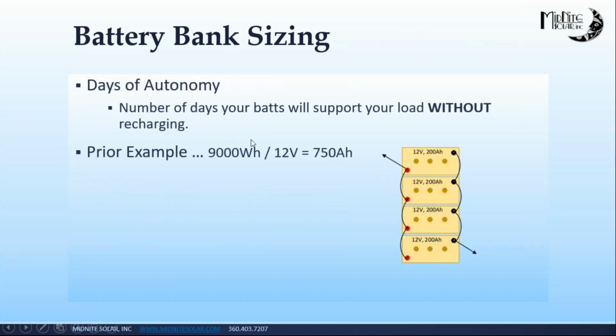Now we spoke about days of autonomy, the number of days your batteries will support your load without recharging. Going back to the load analysis, we need 4,500 watt hours for one 24-hour solar day to support your loads for you and your family. We're going to double it, using flooded or sealed batteries at 50% depth of discharge, so that's 9,000 watt hours. We've decided to stay in 12 volts, so I need a 750 amp hour battery bank. These 4 batteries will give me 1 day of stored energy.